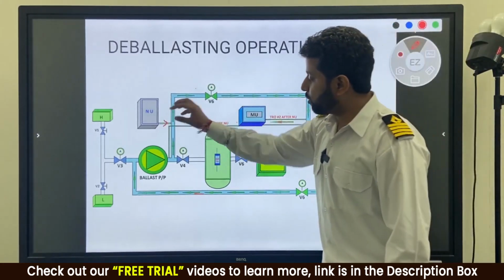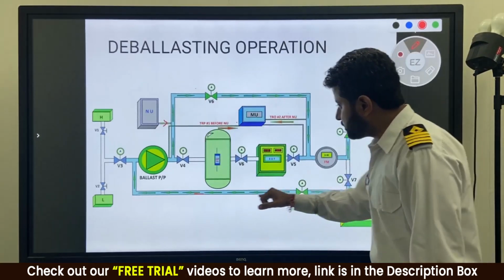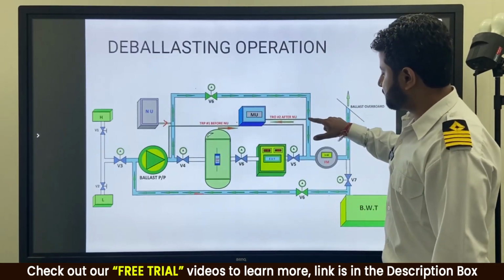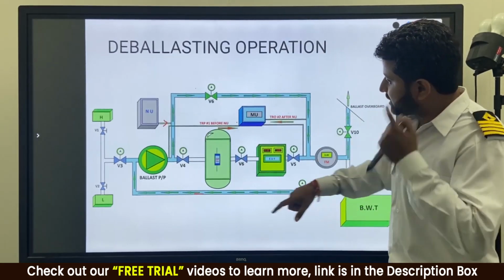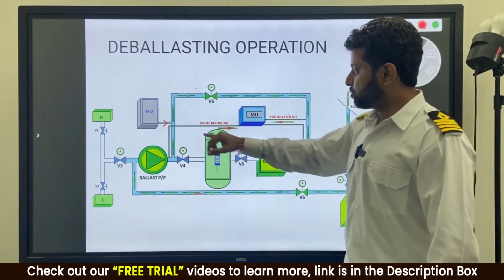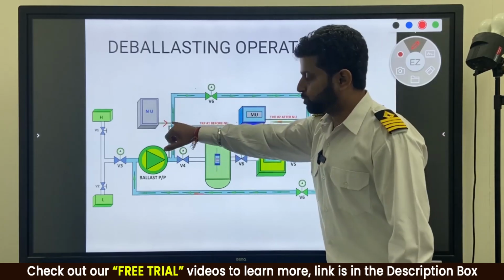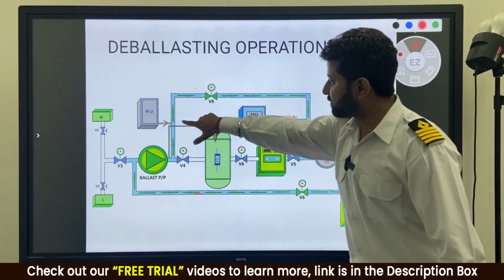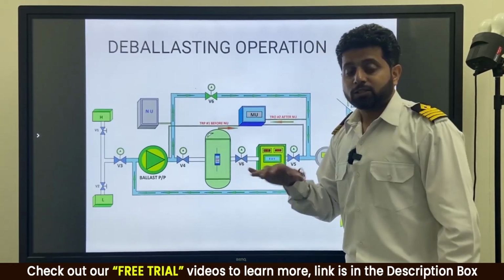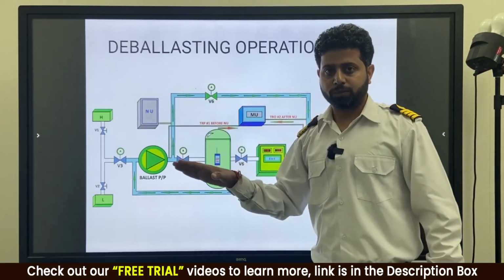So we have to inject only that much neutralizing unit which is sufficient to kill the active oxidants coming from over here. So now we need another sample which comes from over here. So this tells us, bhaiya, initially the sample is 0.2 ppm. Neutralizer unit, you start dosing the chemical, but ensure you dose only this much, that the sample after your dosing from over here is 0 ppm, or even in any case, not just 0, even if it becomes 0.1 ppm, then also this neutralizing unit stops.